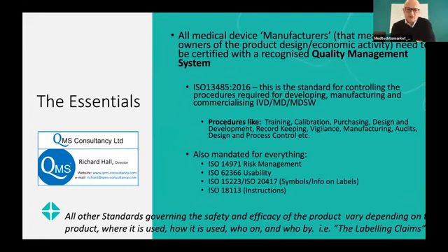Okay, so in terms of the essentials, and I'm still focusing on the process. Before we get into the process of those individual milestones, I still have to give you one last oversight of the regulatory framework in which we operate. Basically, all medical device manufacturers, and the word manufacturer really means owners of the product design or the economic activity, need to be certified with a recognized quality management system in order to submit for IVDR review. That really means ISO 13485, which is the quality management system that governs the development, manufacture, and commercialization of medical devices or in vitro diagnostics.